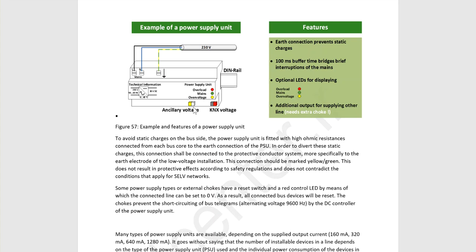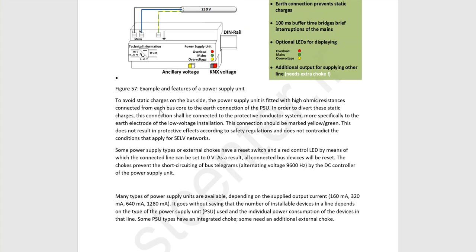Here there are two outputs. One is for most of the power supply units in the market. One is with the red and black, and one is between yellow and white. Remember that the output of the red and black is with choke, okay? But the white and yellow, there is no choke in the output. So if you want to power up another KNX line with this yellow and white, you should always use a choke, okay? You can buy the choke separately from some manufacturers.